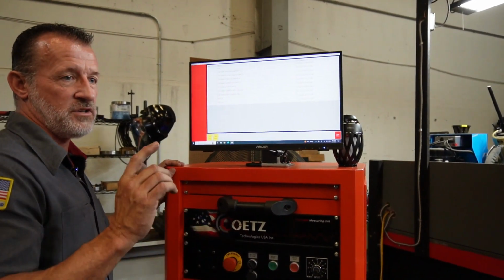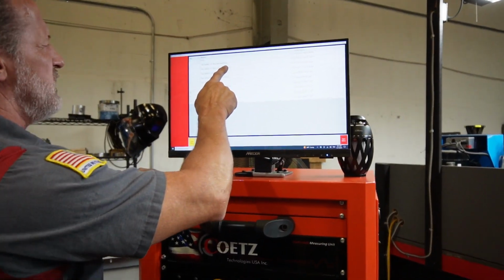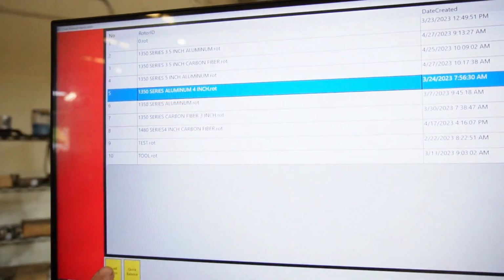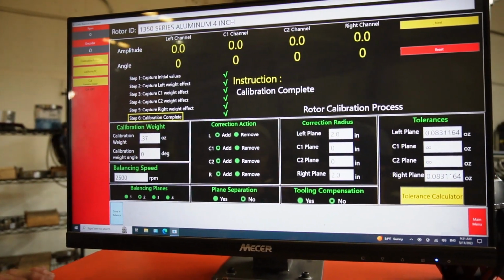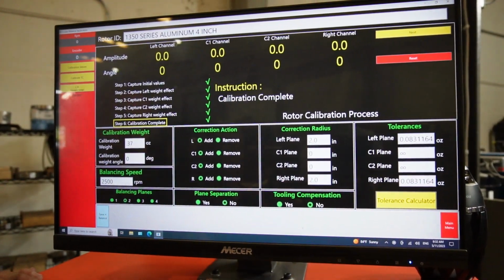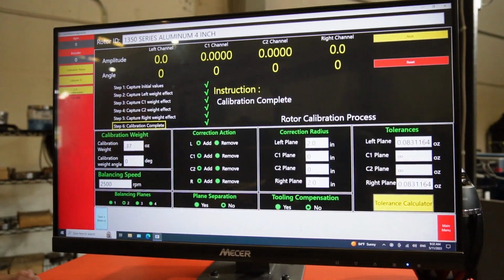So the Trackhawk shaft is a 1350, 4-inch diameter tube, as you can see. So I'll go through the list, find my 1350 series 4-inch aluminum, and click on that rotor index, and load that rotor into the computer. Now all my settings are loaded in, and we're ready to do calibration.